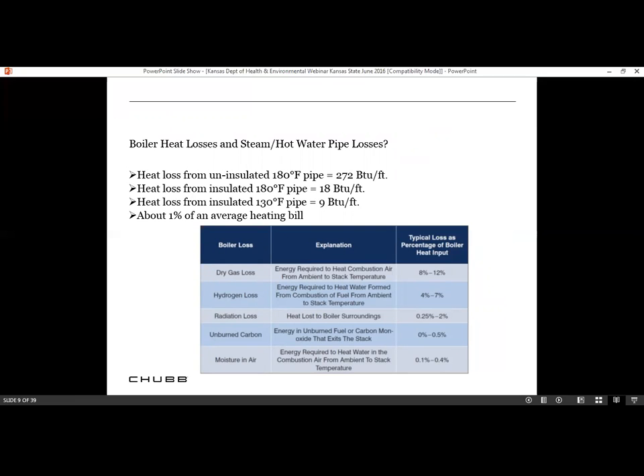But anyway, the heat loss from uninsulated pipe, 180 degrees, you're losing about 272 BTUs per foot. And the heat loss from insulated 180 degree pipe is 18 BTUs per foot. Heat loss from insulated 130 degree pipe is 9 BTUs per foot.